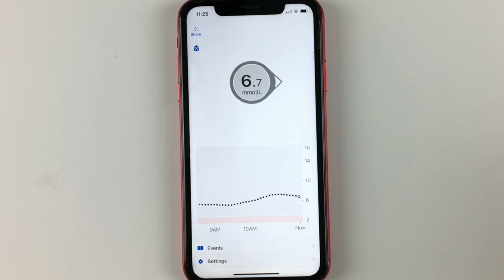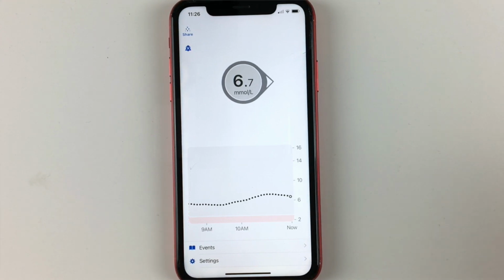Only calibrate when your blood glucose is stable and when your arrow is pointing horizontally to the right, not when your arrow is pointing up or down. When your blood glucose is changing quickly, you will never be able to calibrate it because, as you probably know, the sensor is taking readings from the interstitial fluid, which is lagging approximately 10 minutes behind the readings from blood. So if you calibrate in those moments when your glucose is moving sharply up or sharply down, the blood glucose is already ahead of the sensor and the calibration will never work as good as it would if you are stable.